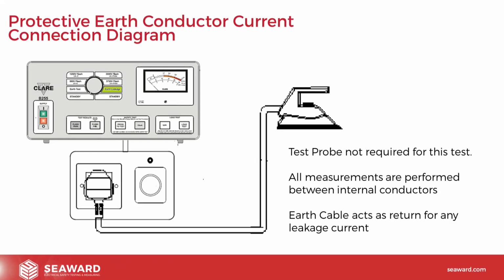So let's have a quick look at the diagram. In this case, we've used the B255, but again, you can see that there's no test probe required for this test. All the measurements, as per a Class 1 insulation or a Class 1 flash test, are all performed between the internal conductors, and it's the earth cable that acts as a return for any stray leakage current.